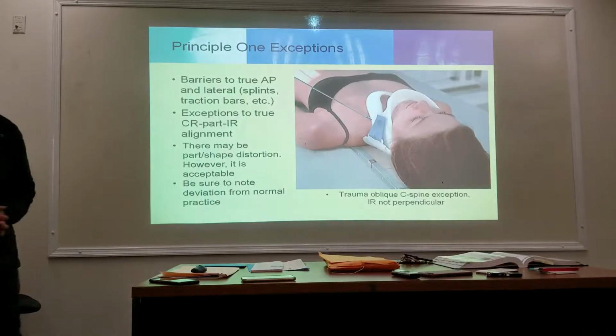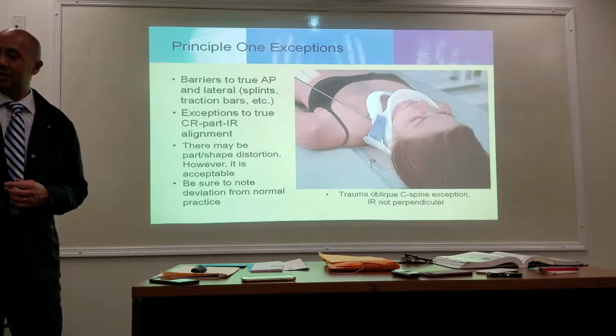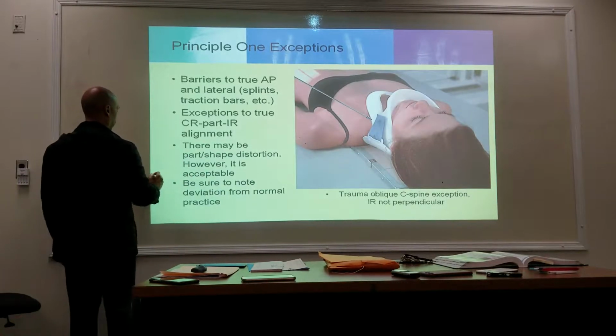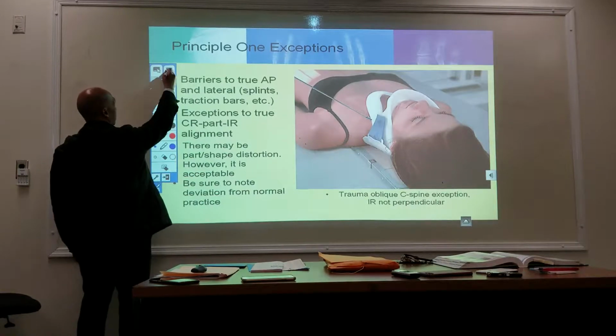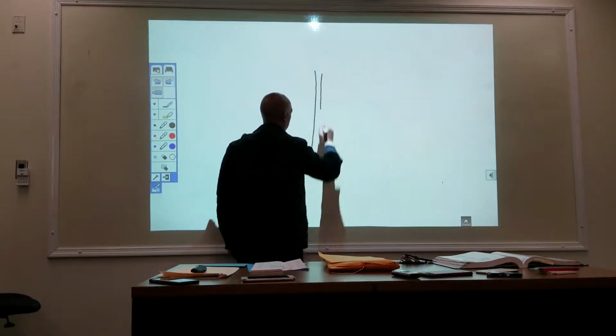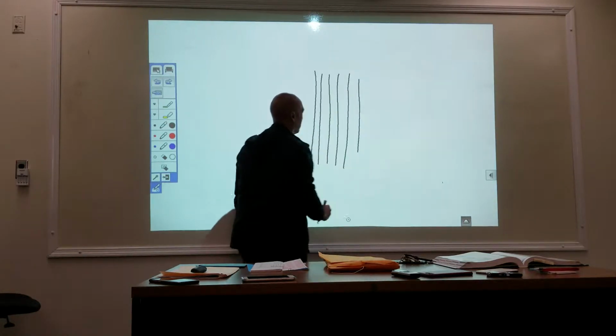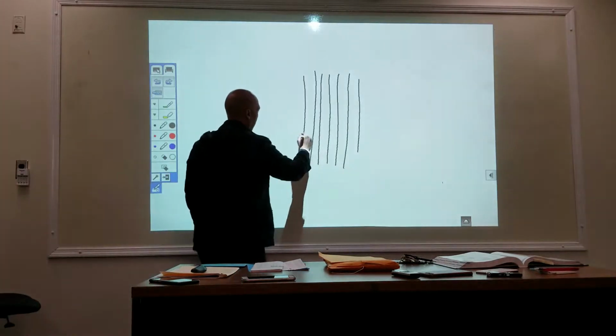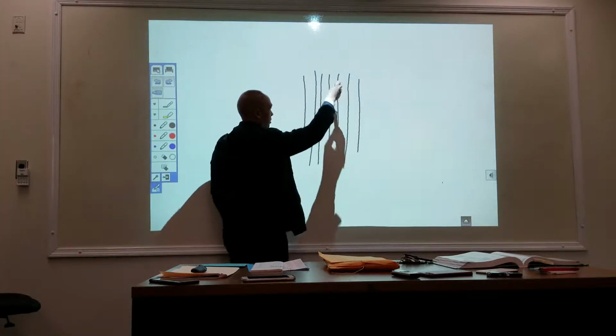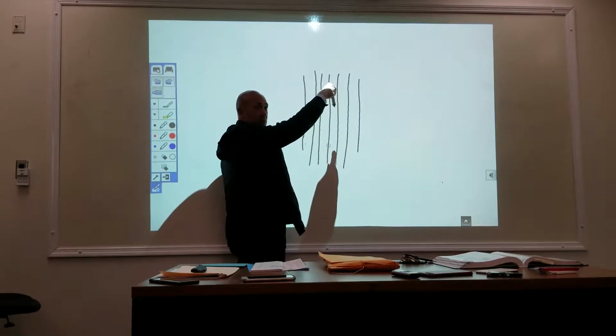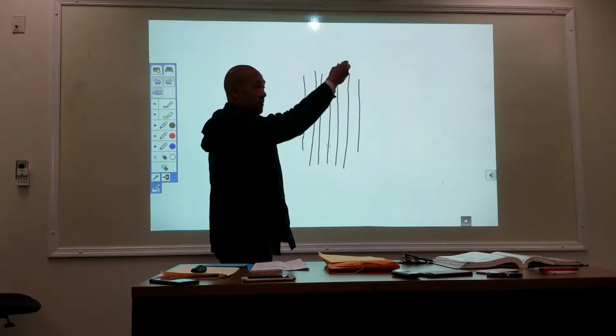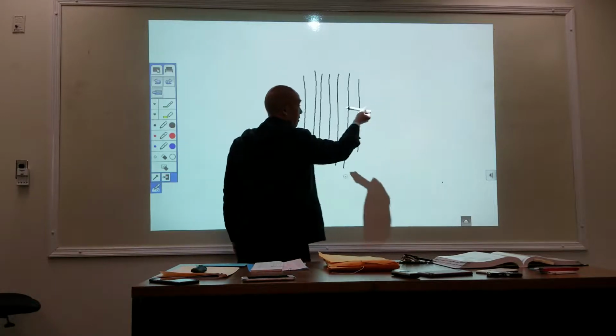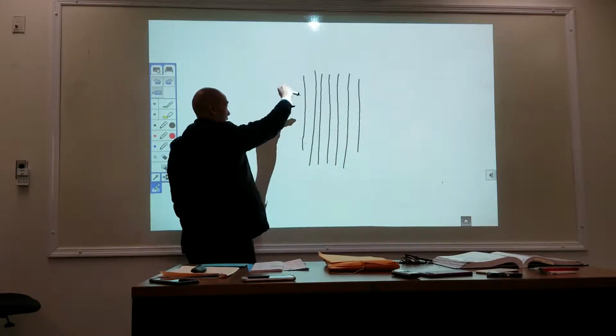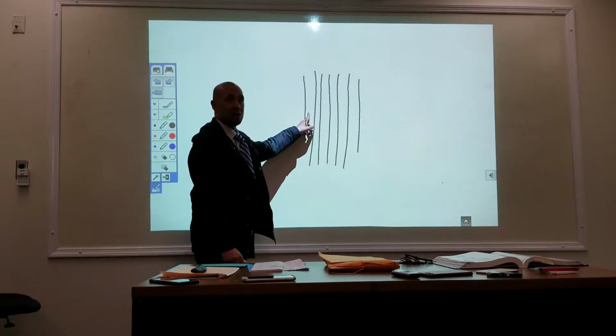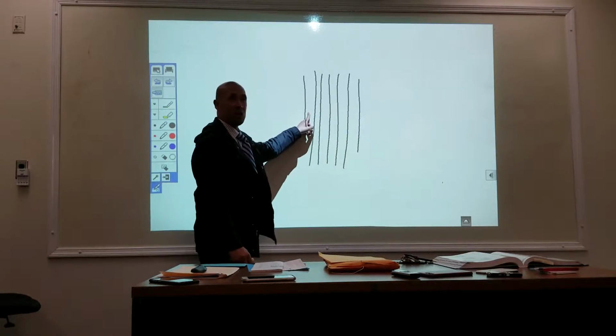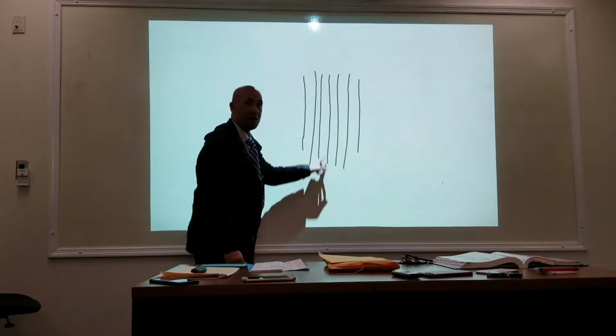Now, when you guys are using grids, I'll talk about this a couple slides down, but I'll just talk about it now. If you're using a grid, remember your grids run the length this way, right? So you can angle this way or this way because you are maintaining the grid line. So your tube angle can go up and down the length of the image receptor. You just can't go from side to side, because if you're coming down at an angle this way, you're going to hit the lead strips. So there is some angulation that is acceptable, but you've got to make sure that the angle of your tube matches the line of your grid.